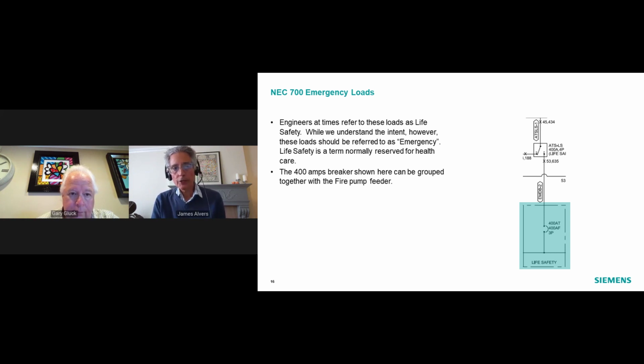700 emergency loads. Engineers sometimes refer to these loads as life safety. And that's kind of understandable since the article explicitly states it's essential for safety to human life. However, this label is really reserved for healthcare generator boards, and that's defined in Article 517. So in this particular case, the one line should be revised to say emergency systems. Assuming these are emergency loads, this breaker would be grouped in a section which would also include the fire pump, as I described earlier. And that's listed in 700.2.